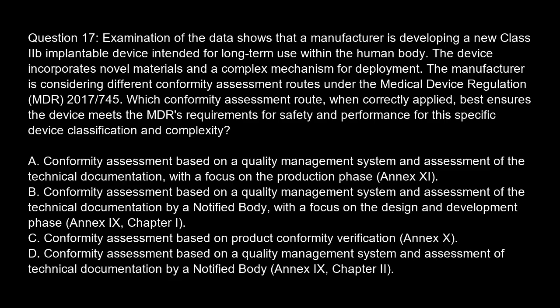Conformity assessment based on a quality management system and assessment of the technical documentation, with a focus on the production phase, Annex XI. Option B. Conformity assessment based on a quality management system and assessment of the technical documentation by a notified body, with a focus on the design and development phase, Annex IX, Chapter I.